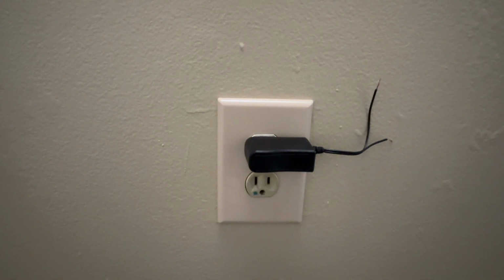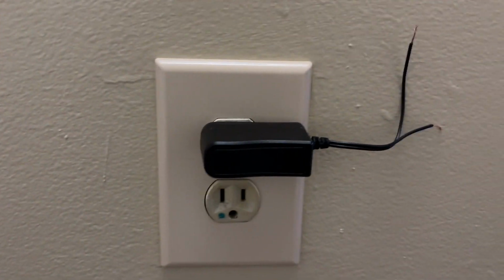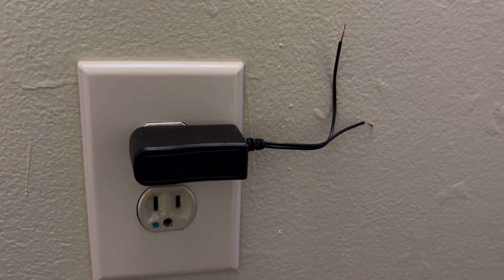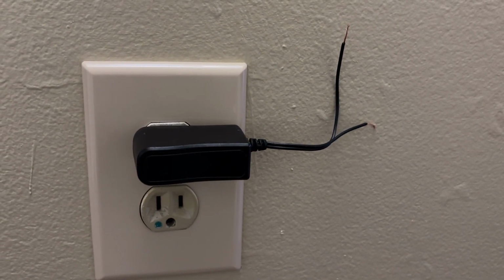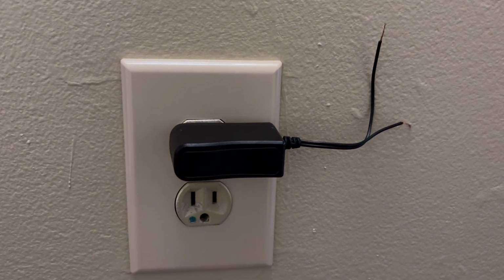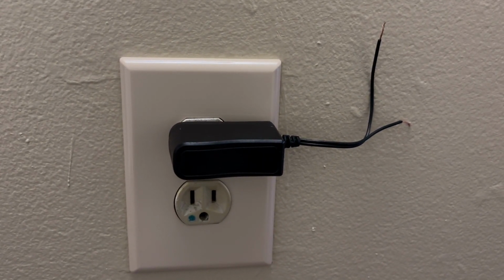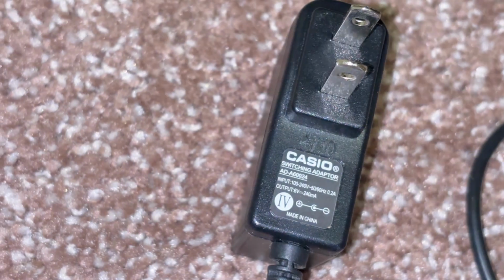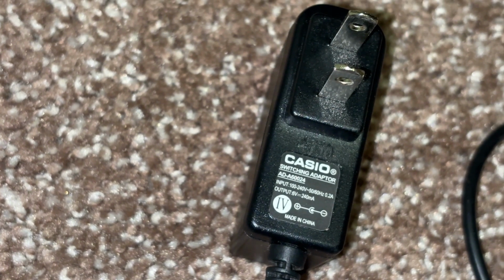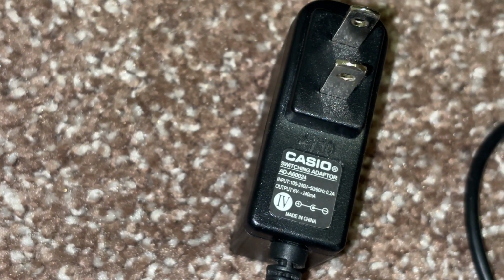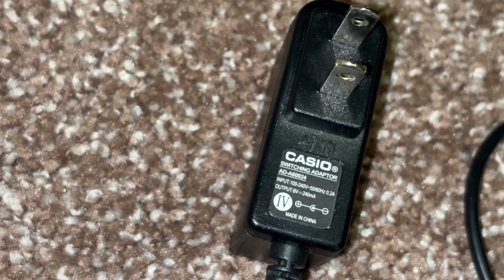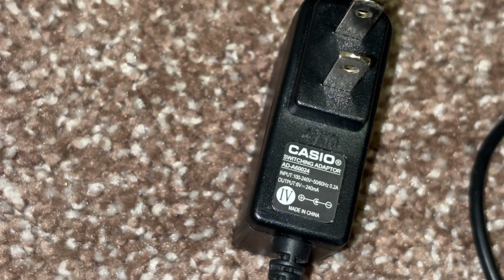On some emergency pull cord systems, you will have a plug-in style instead of a standard transformer, which simply looks like a plug that someone cut the end of the wires off. On these, we need to read them and verify if they are switching adapters or switching converters, which would mean it turns AC into DC. So on this one, we can see that it is a switching adapter, which takes 100 to 240 volt input, and it outputs at 6 volt.